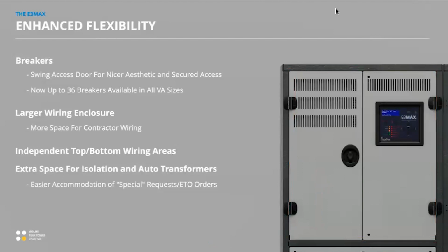As you saw in the previous slide, we've totally isolated the top and the bottom, and that bottom space is actually a lot larger. Today we use it for all of the inverter modules - the big transformers, the big heat sinks, and so on. But it gives us more flexibility for special requests or ETO orders. The one that immediately comes to mind is using isolation transformers for mixed output voltages, which comes up all the time, sometimes to my chagrin. It gives us that flexibility without needing an additional dedicated transformer cabinet next to it.